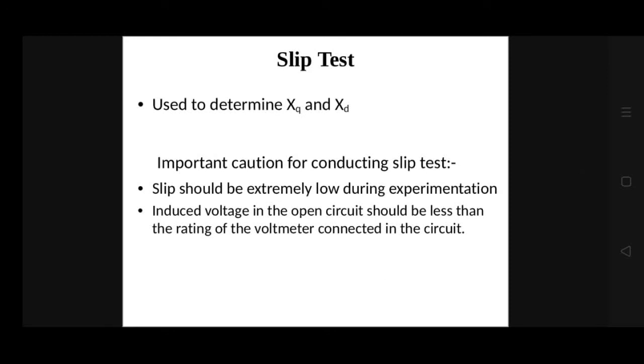Now let us discuss how to find the values of XD and XQ using the slip test. The slip test is carried out on a salient pole machine and there are some important cautions for conducting it. First, the slip should be extremely low during experimentation. In the case of high slip — more than about 5% — the following effects may be observed: current induced in the damper winding will produce an appreciable error, and the induced voltage in the open circuit field may reach a dangerously high value. It should also be assured that the induced voltage in the open circuit is less than the rating of the voltmeter connected in the circuit.